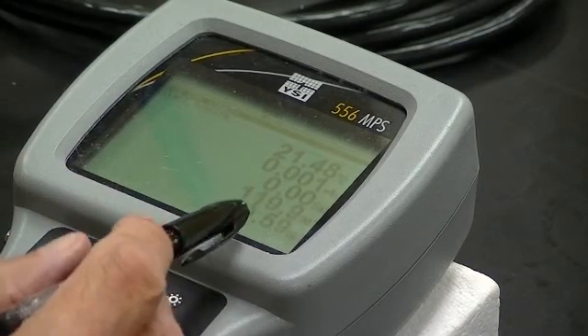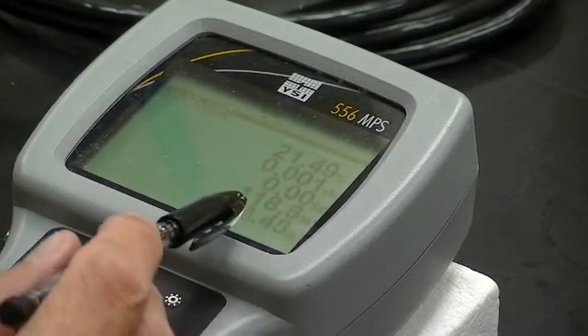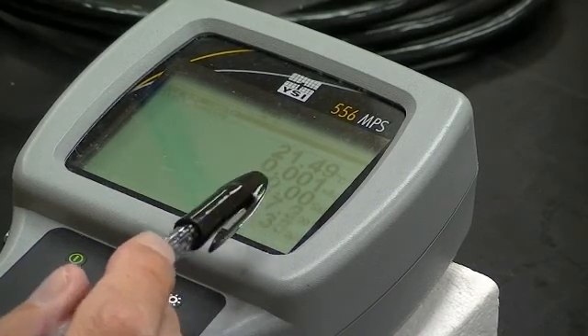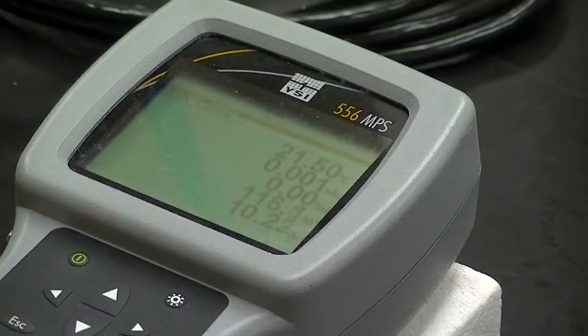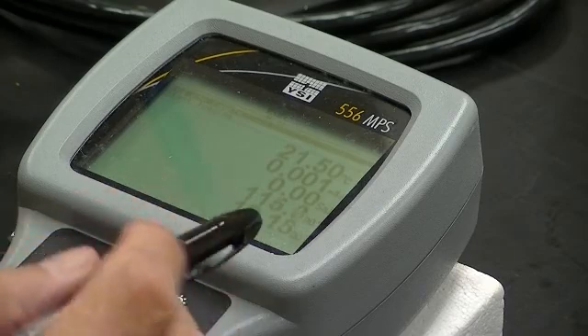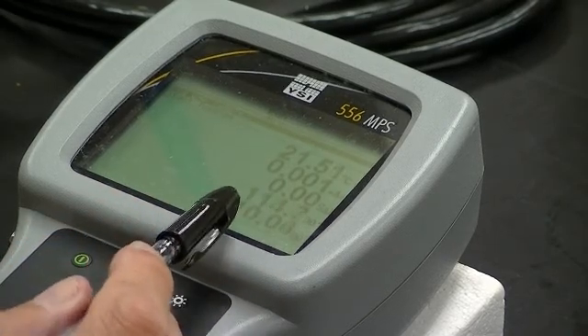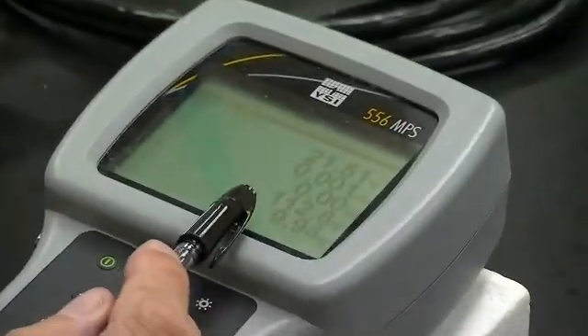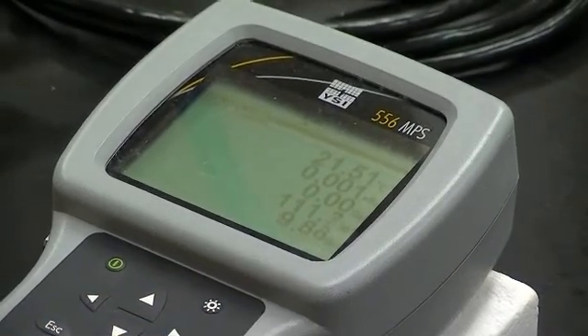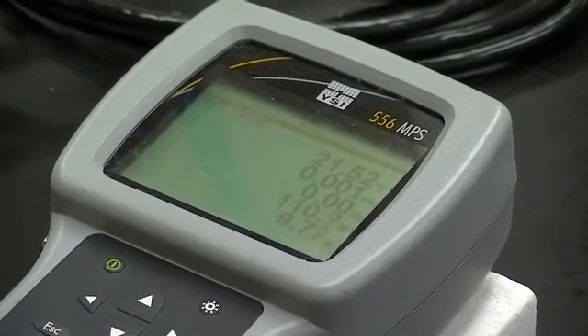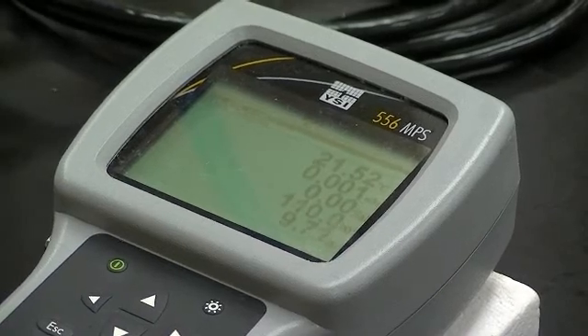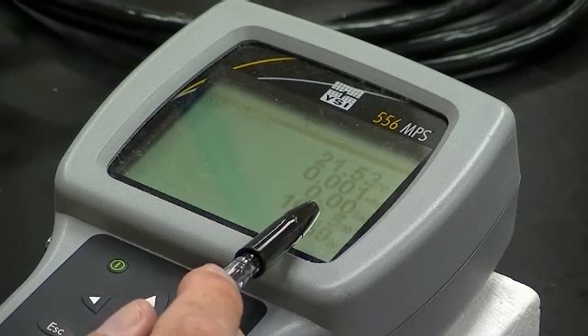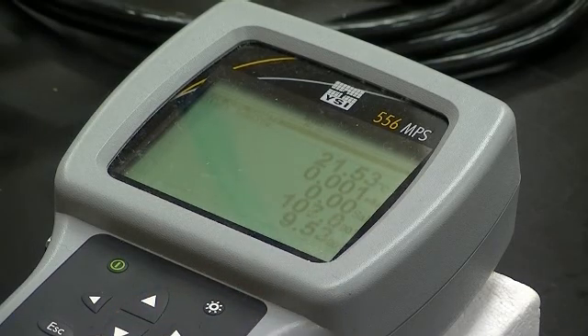And notice these numbers, if you can see them, are tumbling rapidly. They start high, and when you turn the instrument on, they come down and stabilize. So this is passing through 113%, 111, and we just let it sit. Now it's gone to 109. And when it stabilizes just a little bit, it doesn't have to be completely stable at this point, we'll go ahead with the calibration.